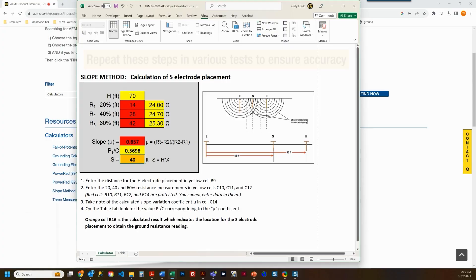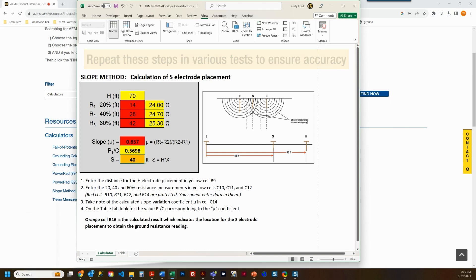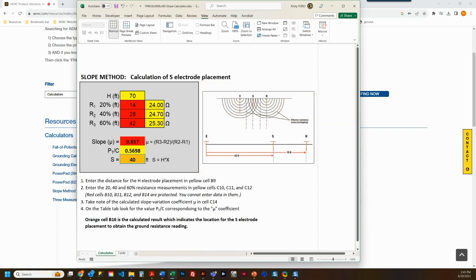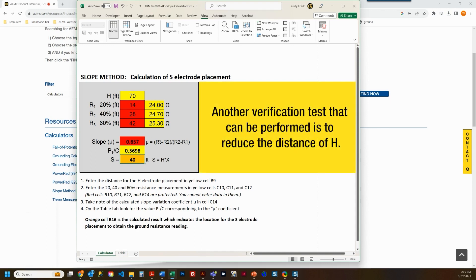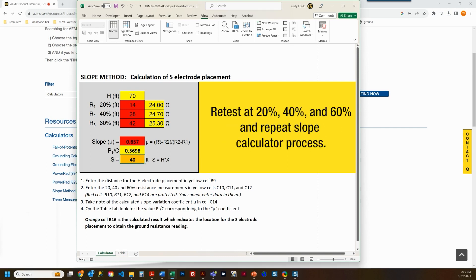AEMC Instruments recommends that you repeat these steps in various orientations to ensure accuracy. One variation to verify accuracy is to turn the test 90 degrees, or a minimum of 30 degrees, and repeat. This allows you to validate the results against the original test. Another verification test would be to reduce the distance of H, retest at 20, 40, and 60 percent, and repeat the slope calculator process. These measurements should be within a few percentage points of each other.